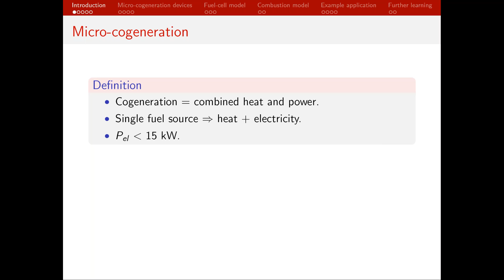So for starters, what is micro-cogeneration? It is a form of cogeneration, or combined heat and power, where we're taking a single fuel source, typically natural gas but not necessarily, and converting that to heat and electricity within the building site. Cogeneration exists on many different scales, from large-scale systems down to micro-scale systems. Typically, the term micro-cogeneration applies to systems with electrical power outputs less than 15 kilowatts, small enough to be placed within a residential building, a single-family house, or a small multifamily building.